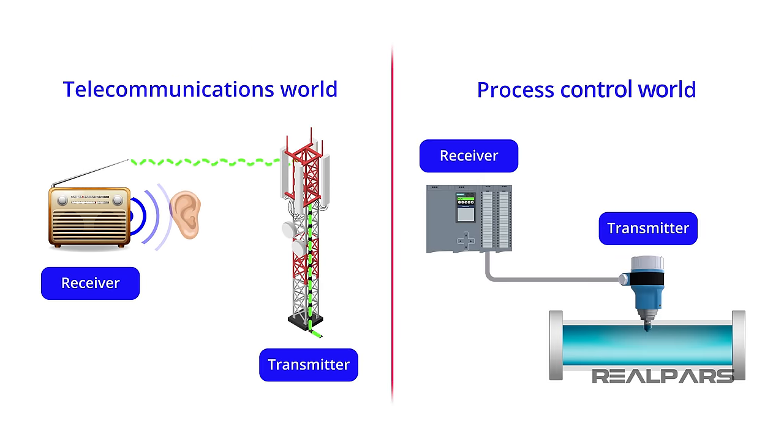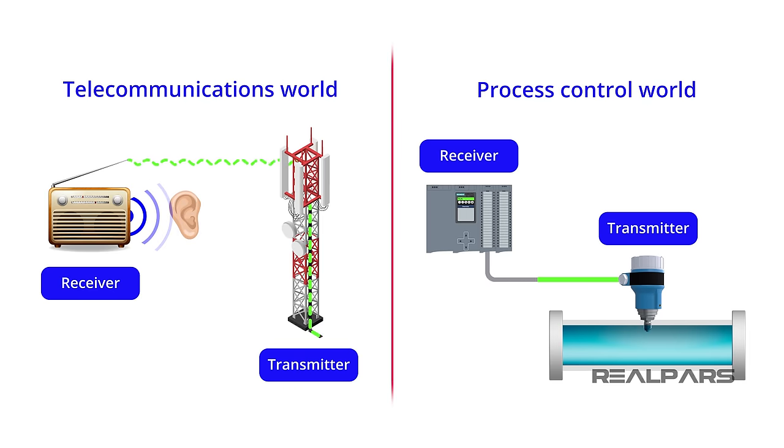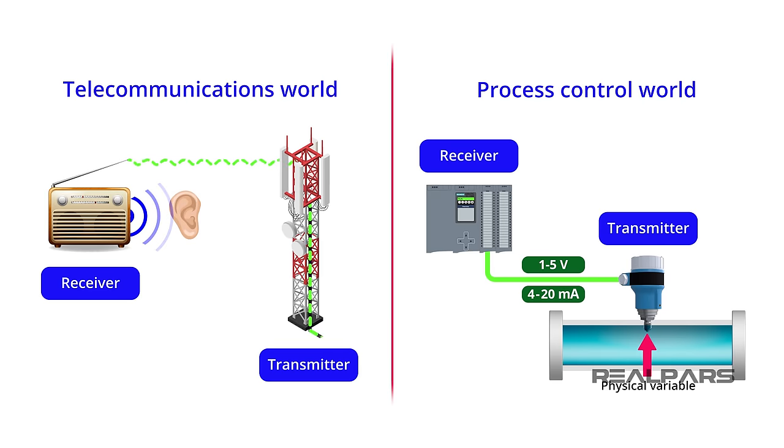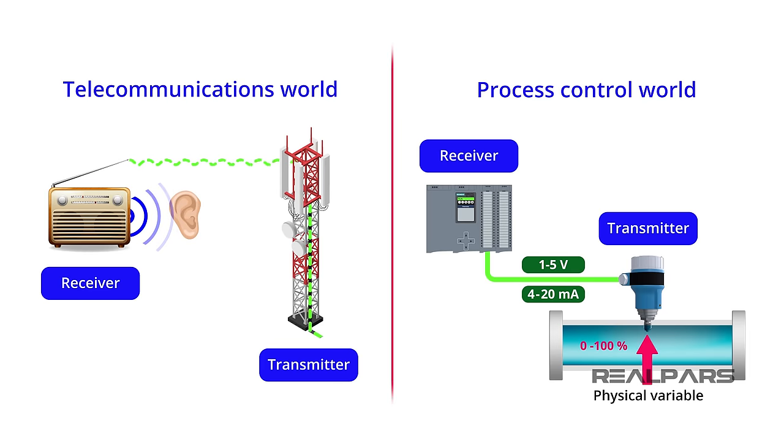In the world of Process Control, a Transmitter is a device that transmits a standard instrumentation signal representing a physical variable being measured. The standard electrical signals are 1 to 5 volts or 4 to 20 milliamps, which represents 0 to 100% of the physical variables being measured. This transmitted signal is detected by a receiver, such as an analog input on a PLC or a DCS.